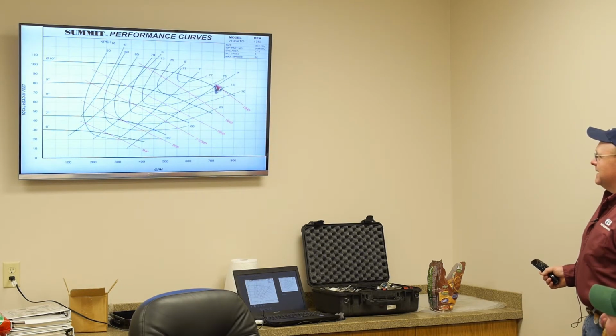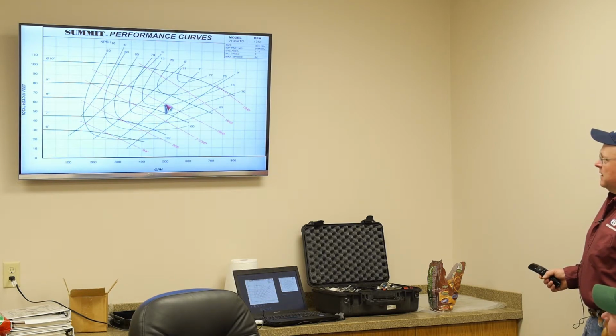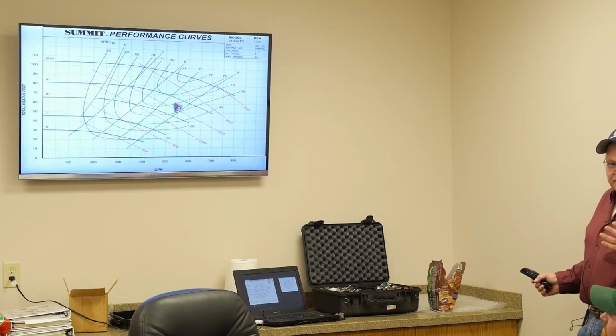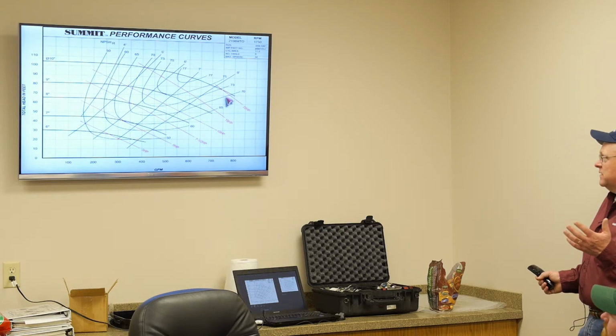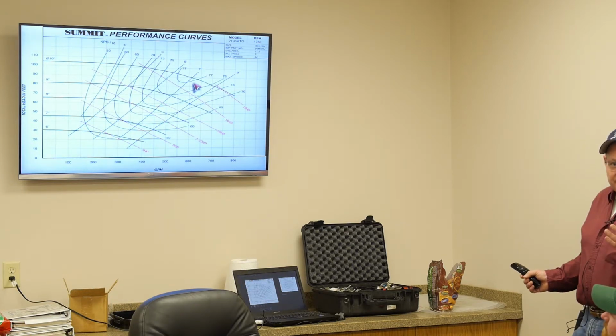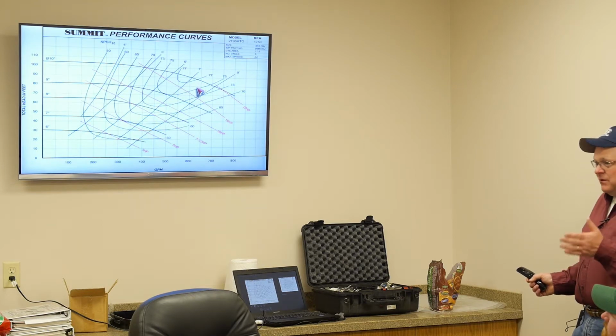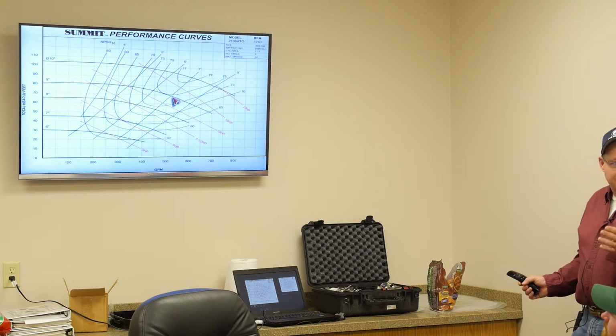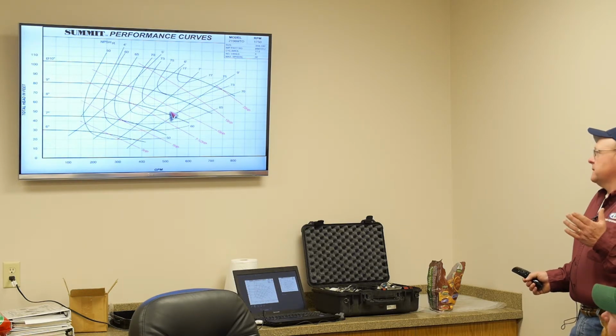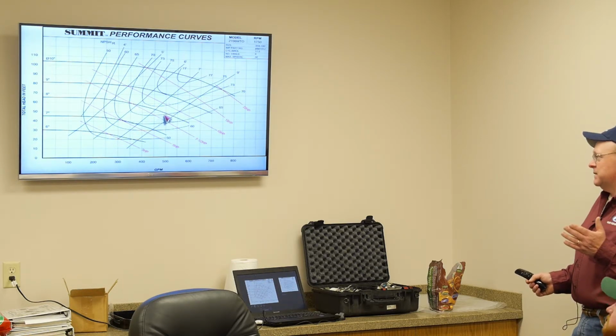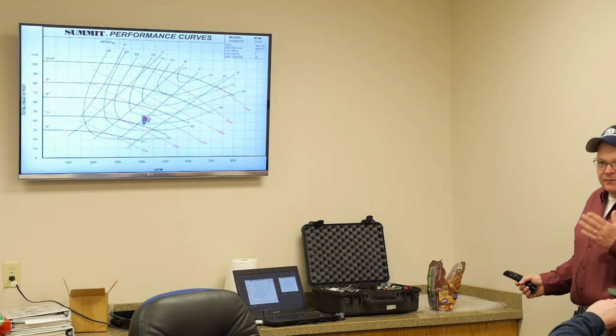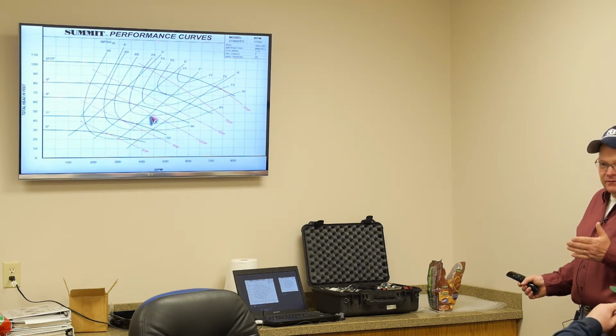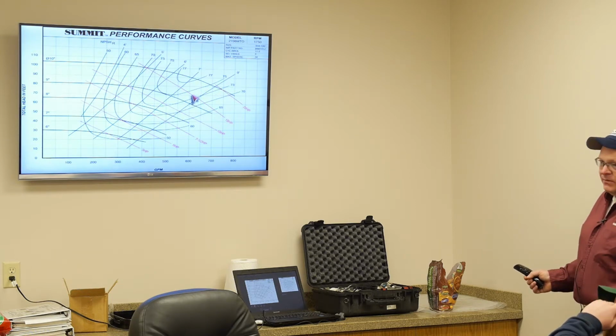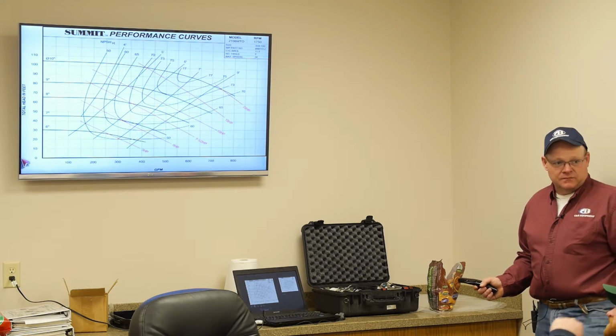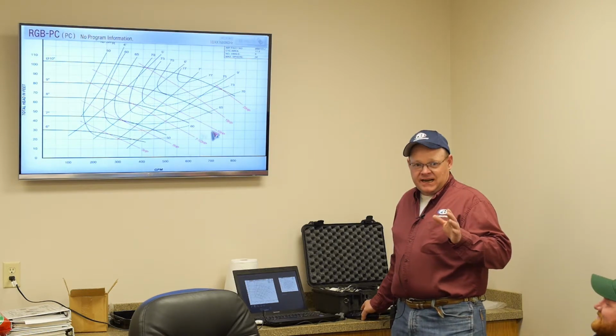But anyway, so you understand, and we're not all on the purchasing side of it, but the difference between a 10 horse and a 20 horse is minimal. I mean, if you're going to buy a 10 horsepower motor, even though you're doubling horsepower, it really doesn't cost that much more. Depending on who's on the front side in the purchasing department, and they're always cutting pennies, they'll squeeze every last cent out of it. But we always try to give you plenty of horsepower when we're sizing a pump. So just know and understand that can happen to you.